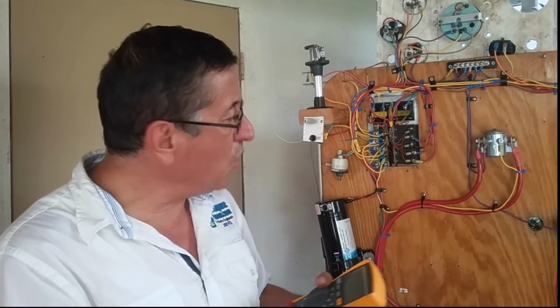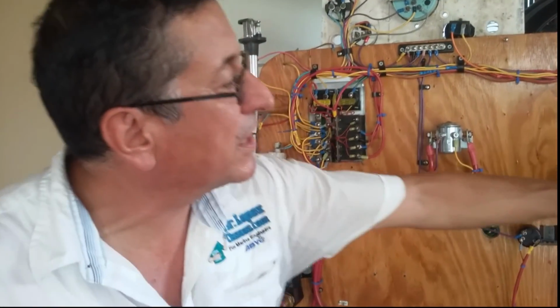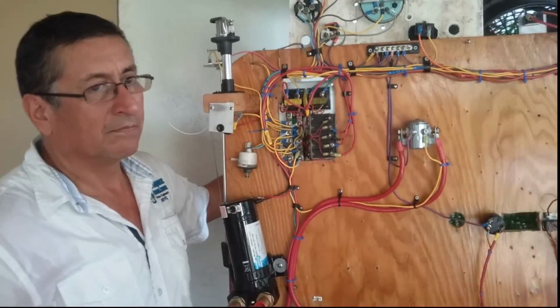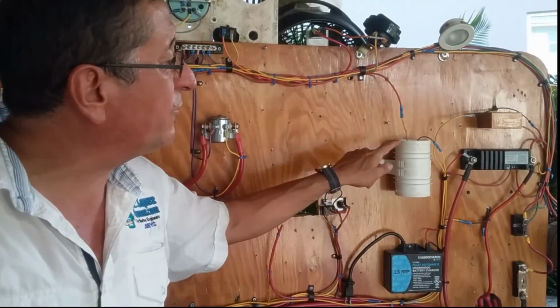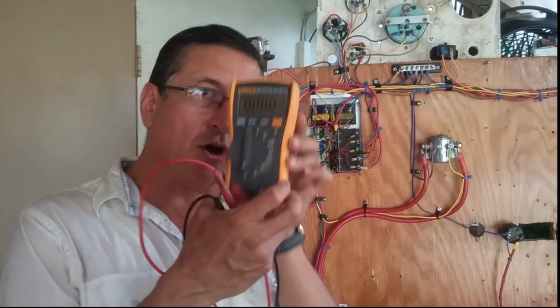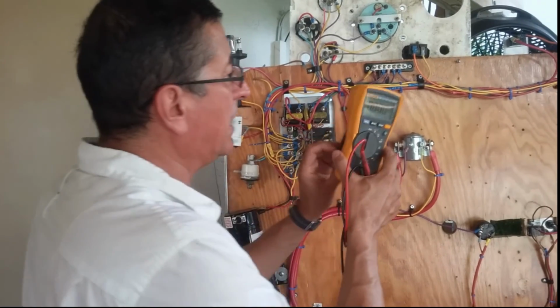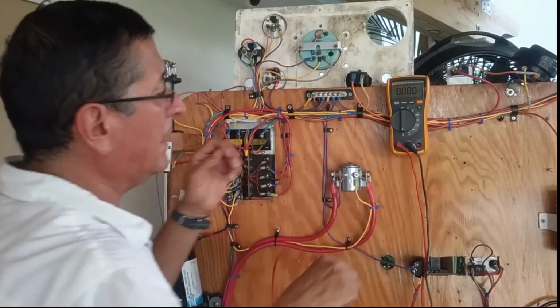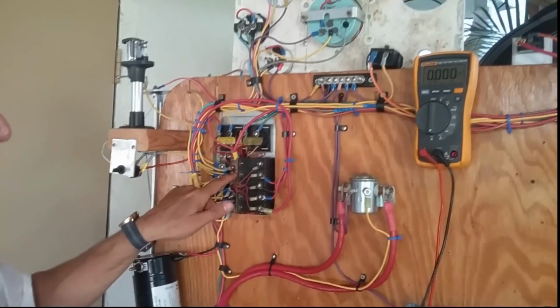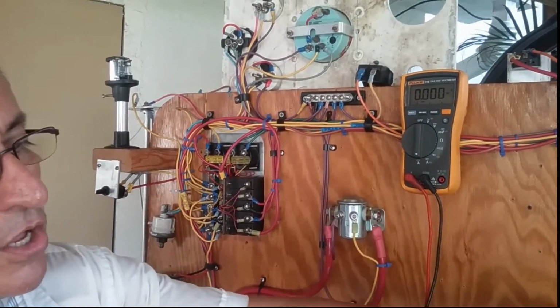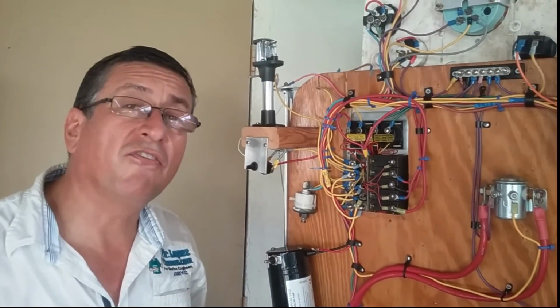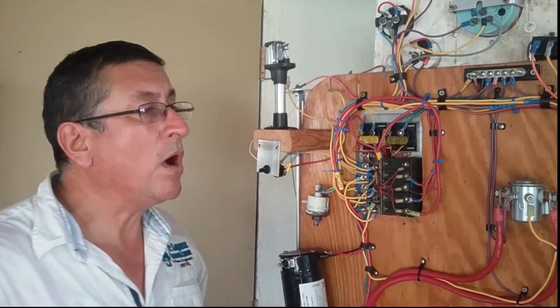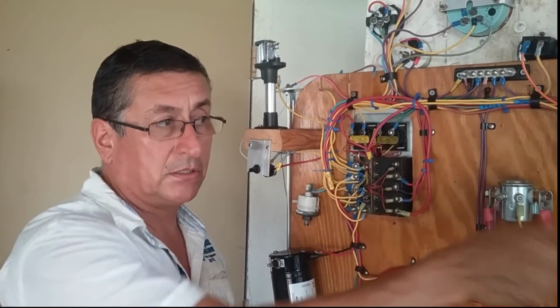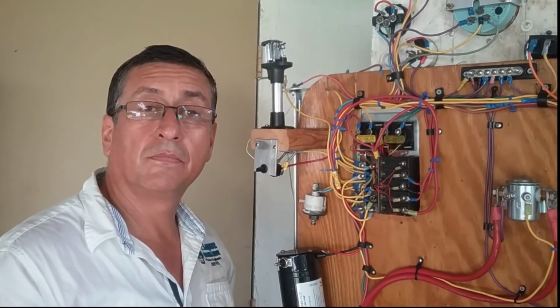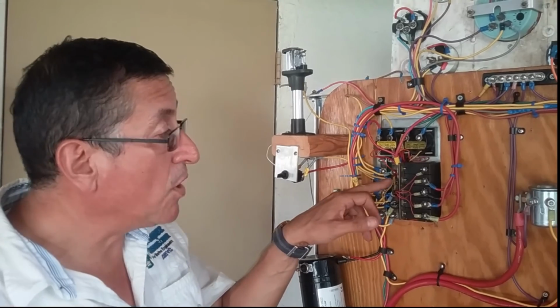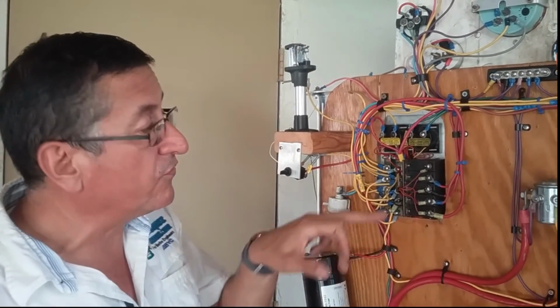For example, I want to know about breaker number 2, the breaker for the blower. I want to know what is the consumption of this blower when the blower is running. I am going to use my ammeter. Okay, I am going to put my ammeter here, and at this moment the breaker for the fan is off. The fan is not running. What happens when I close the contact on the breakers? The fan starts.